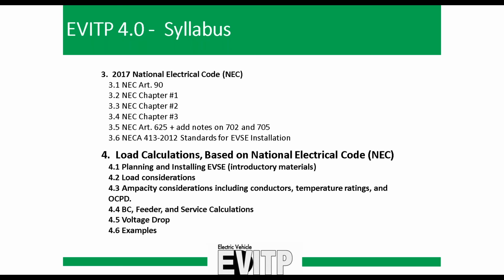Module 4 covers load calculations for the proper sizing of conductors supplying electric vehicle supply equipment. By properly sizing the conductors, we can avoid those fires that Bernie spoke to. In Module 4, we're going to look at planning and installing EVSE, load considerations, ampacity including conductor temperature ratings, and overcurrent protection devices, branch circuits, feeders and service calculations, voltage drop calculations, and we'll wrap up Module 4 with a series of examples.